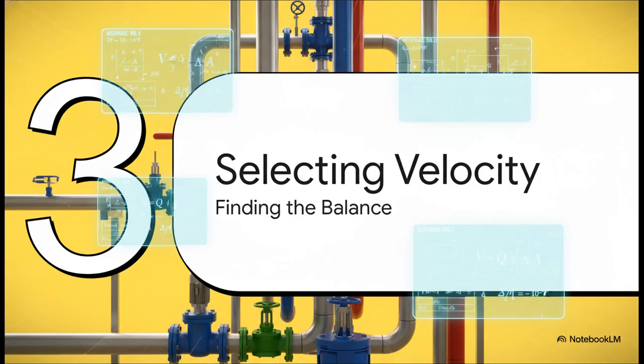So let's say our building needs 100 tons of refrigeration. You just multiply that by 2.4 and boom, you get your answer. The system has to be designed to move 240 gallons of water every single minute. Okay, so we know how much water we need to move. The next big question is, how fast should that water be moving through the pipes? This is a critical decision.